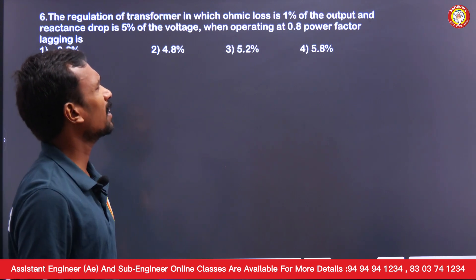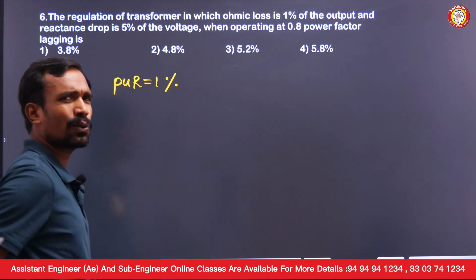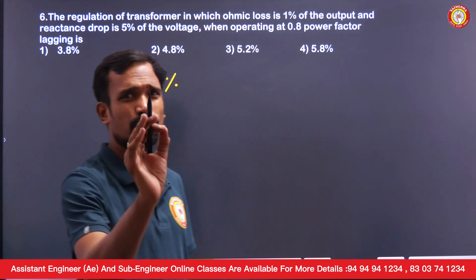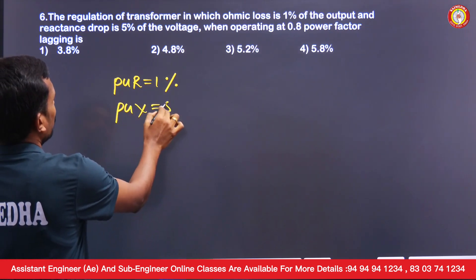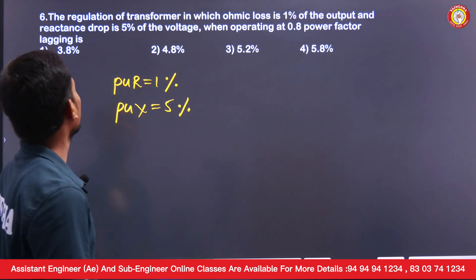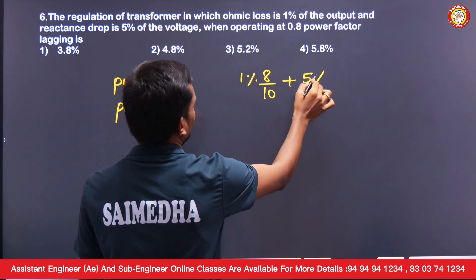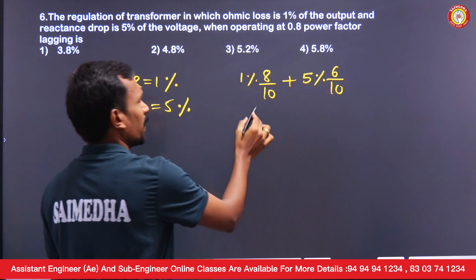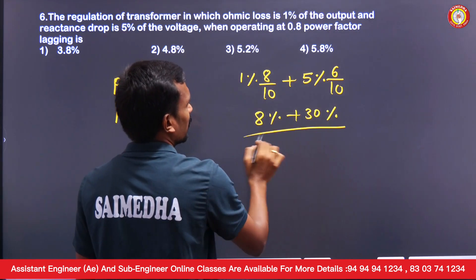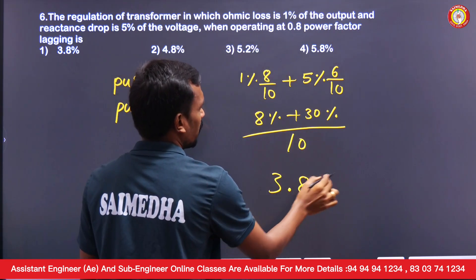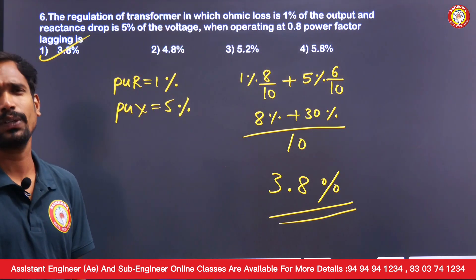Next question: the regulation of a transformer where ohmic losses are 1%. Remember: ohmic losses equals per unit resistance. Voltage regulation at 0.8 lagging power factor = per unit R × cos φ + per unit X × sin φ = 8%/10 + 30%/10 = 38%/10 = 3.8%.